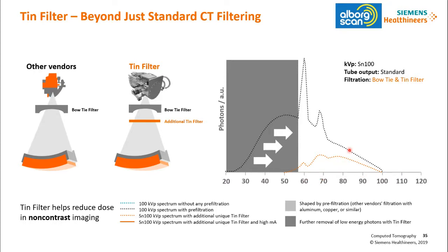So that is the high power mA technology. Every CT scanner on the Siemens Go platform, we made with an iterative reconstruction algorithm as standard. So our SAFIRE algorithm is standard. Whenever you reduce the dose, the noise increases, which means a waste in the image. So what we have done is standardize every system. SAFIRE is standard in every imaging. It will reduce the noise from the unwanted quanta also. So the combination of the tin filter, high power mA, and the SAFIRE iterative reconstruction algorithm together will help you reduce the dose drastically. I hope I answered your question.